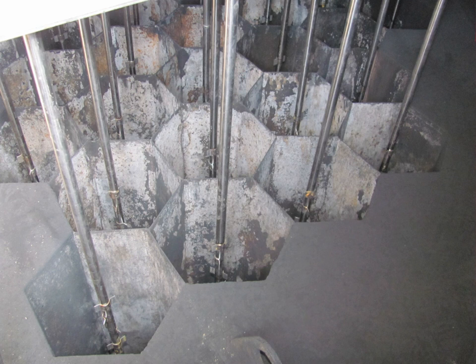The same thing is believed to occur in laboratory measurements. Parallel plate geometry is used in laboratory measurements without corona generation. A stainless steel cup holds the sample. Another stainless steel electrode weight sits on top of the sample, in direct contact with the dust layer. As voltage is increased from small amounts, e.g. 20 volts, no current is measured. Then, a threshold voltage level is reached. At this level, current surges through the sample, so much so that the voltage supply unit can trip off. After removal of the unburned combustibles during the above-mentioned annealing procedure, the descending temperature mode curve shows the typical inverted V shape one might expect.